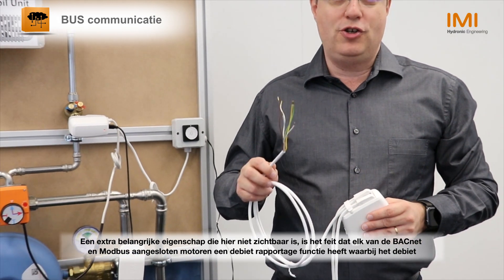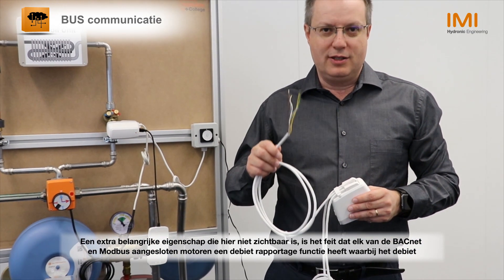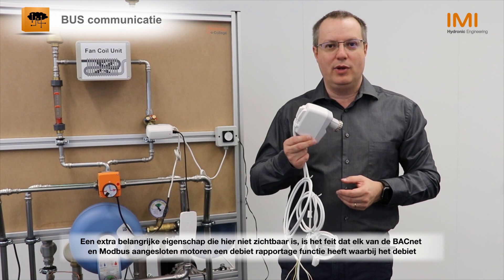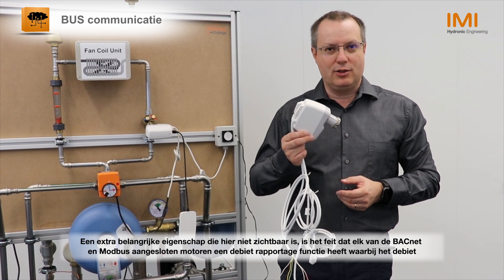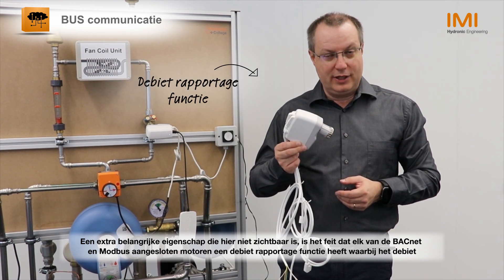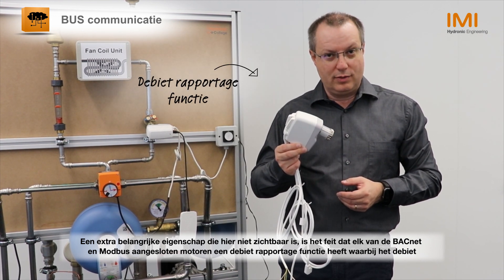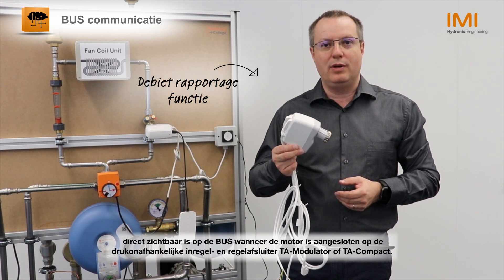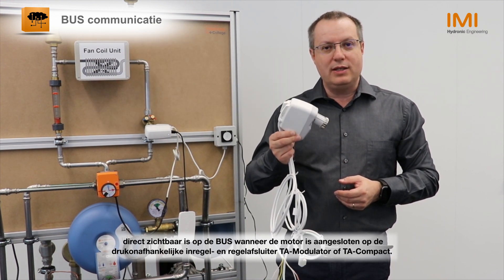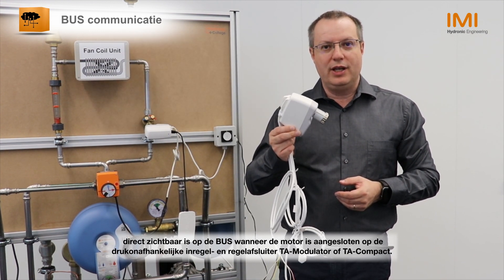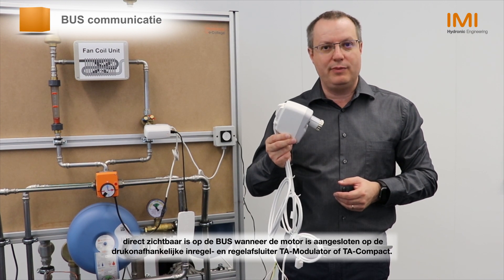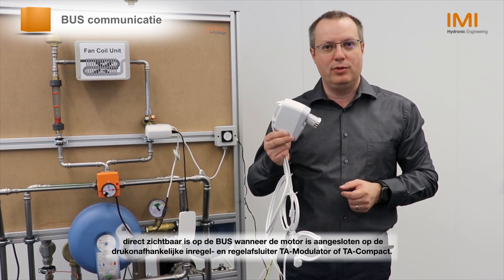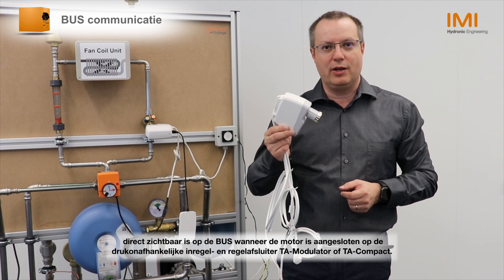One additional key feature that is not visible here is the fact that each of the BACnet and Modbus connected actuators has a flow reporting function, whereby the flow is directly visible on the bus line when the actuator is connected on a pressure independent balancing and control valve, such as TA modulator or TA compact.